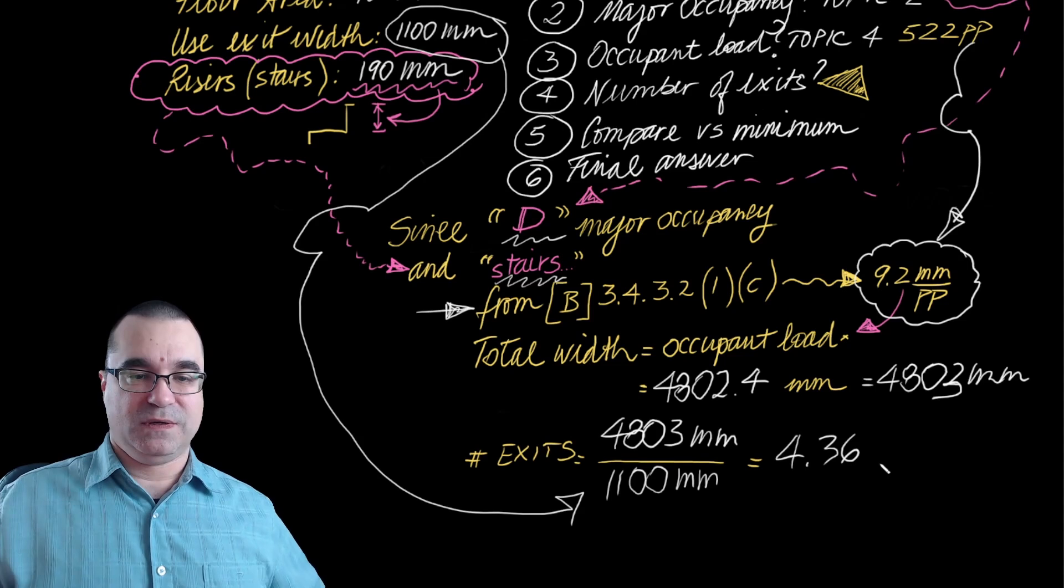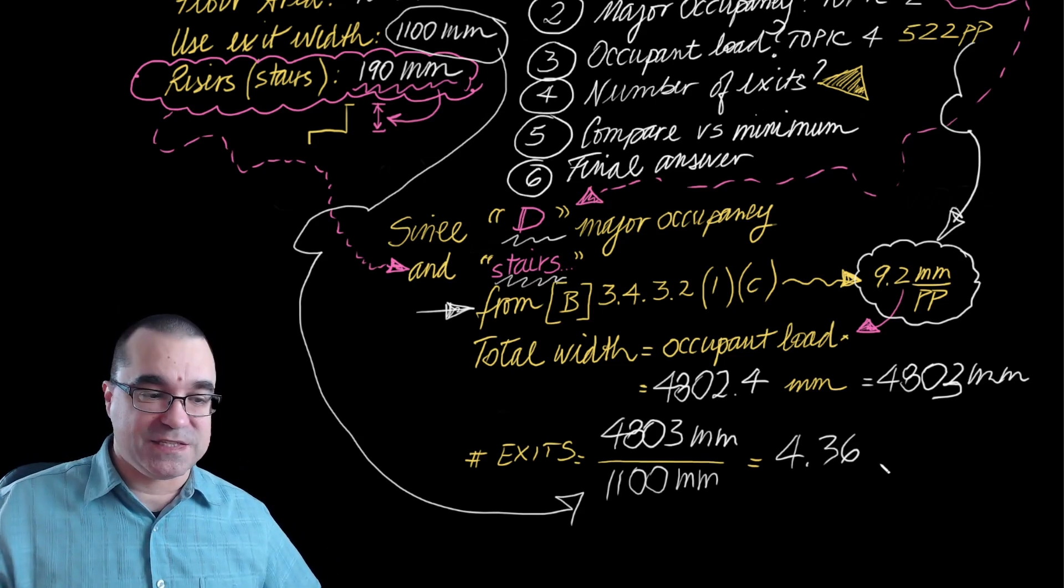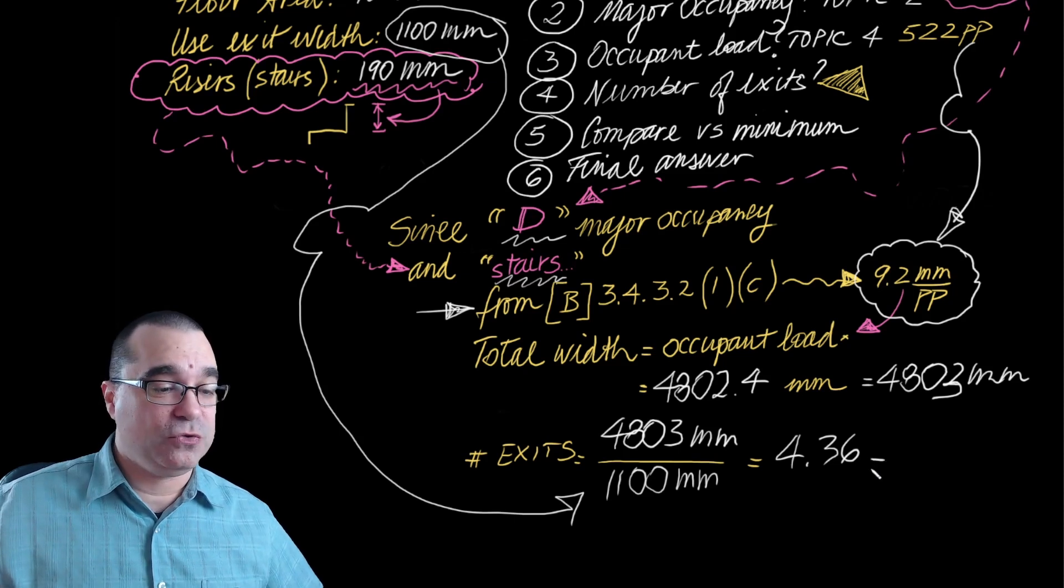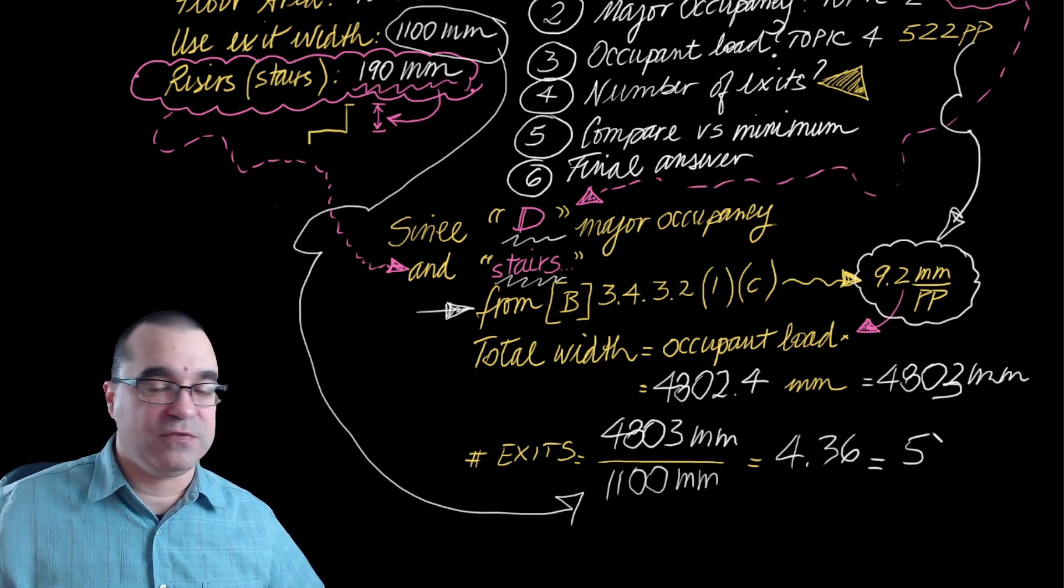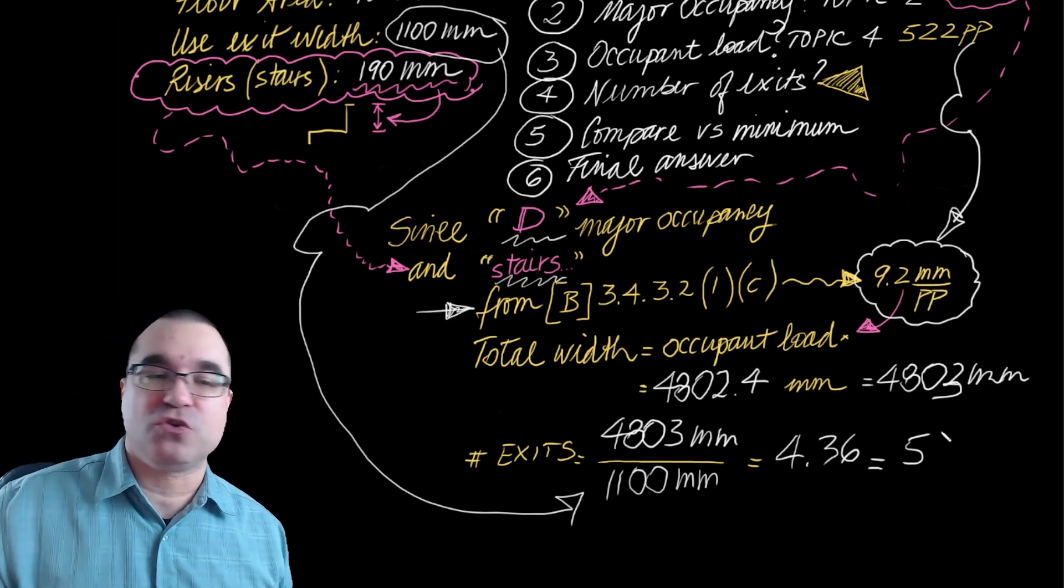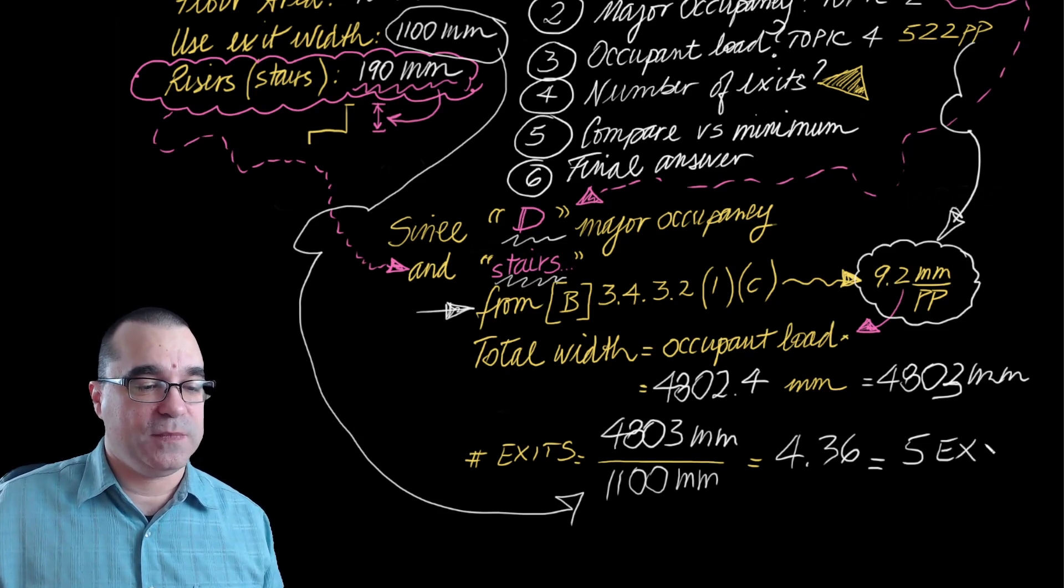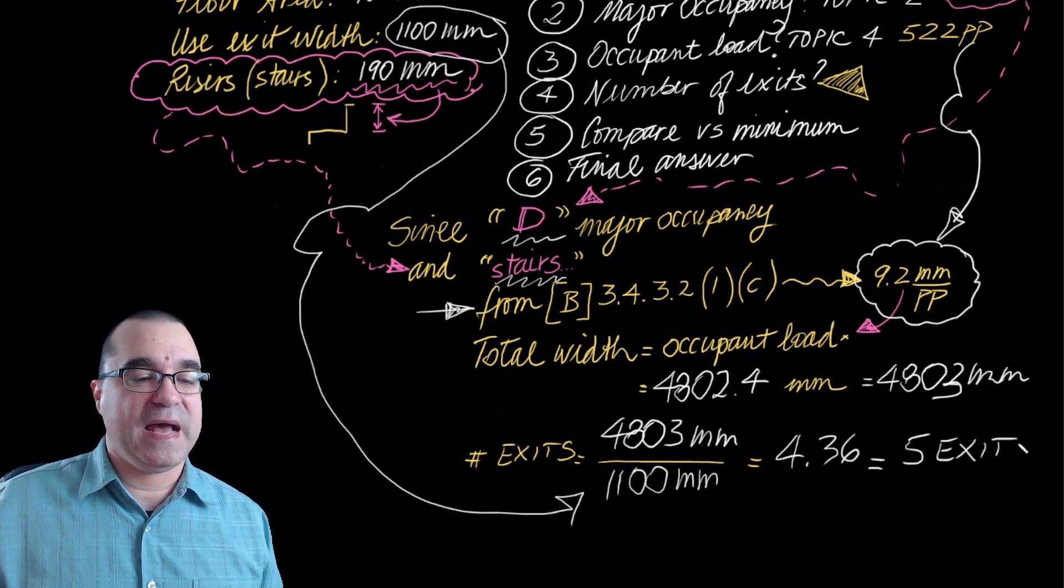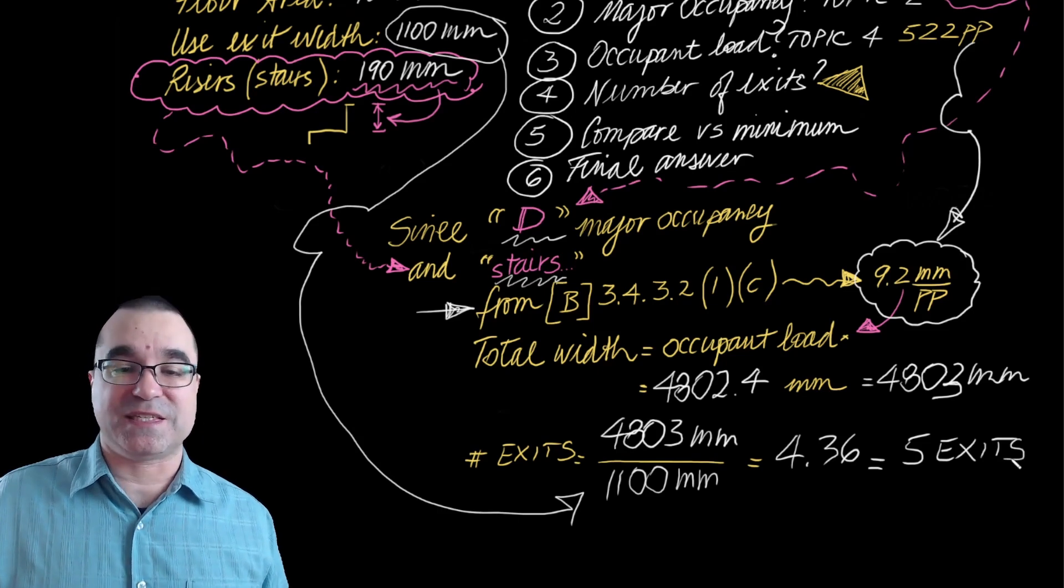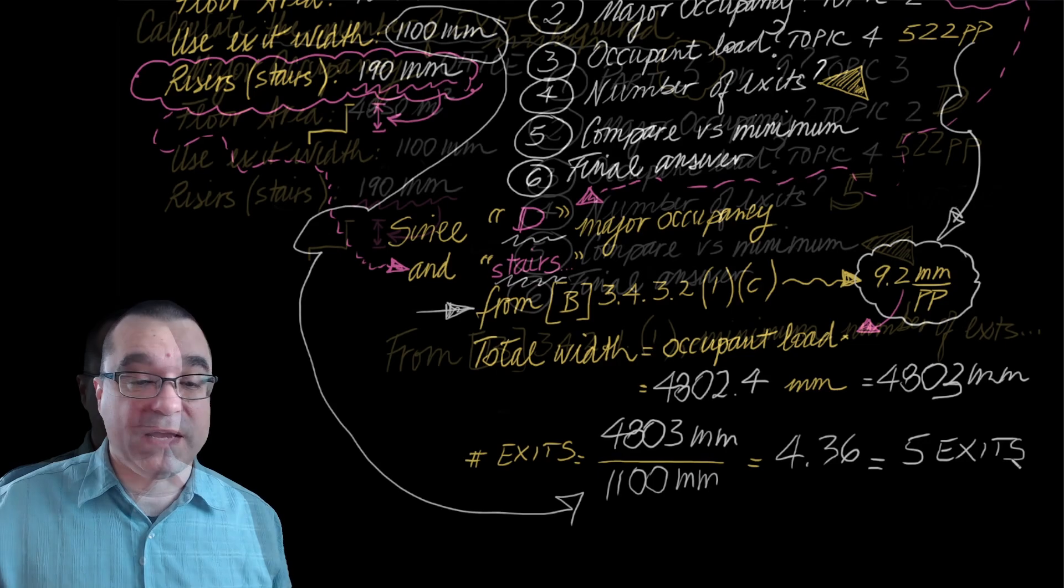Now, this means more than four exits. So what you do is you have to round up to five. You don't round down the number of exits because then you're not serving all 522 people. So what we get is based on this information we have right here, we need at least five exits. That's step number four. Let's move on to step number five.